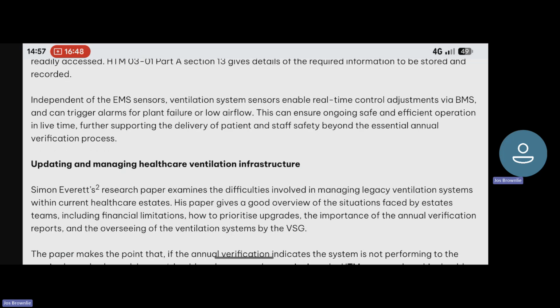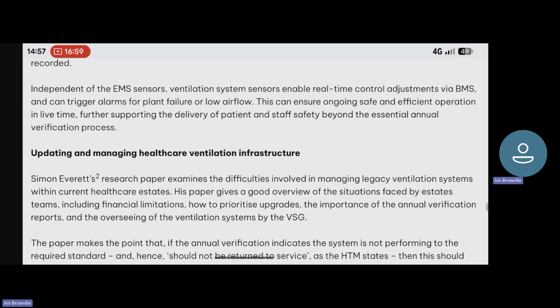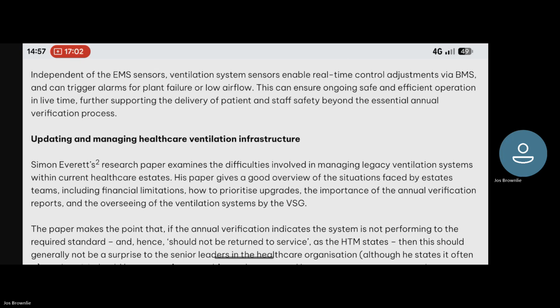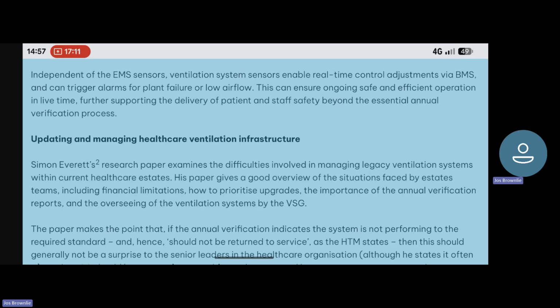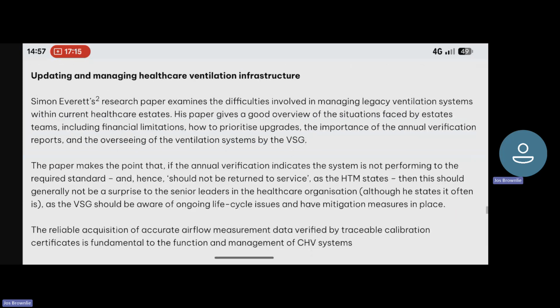Independent of the EMS sensors, ventilation system sensors enable real-time control adjustments via BMS and can trigger alarms for plant failure or low airflow. This can ensure ongoing safety and efficient operation in live time, further supporting the delivery of patient and staff safety beyond the essential annual verification process. Updating and managing healthcare ventilation infrastructure.